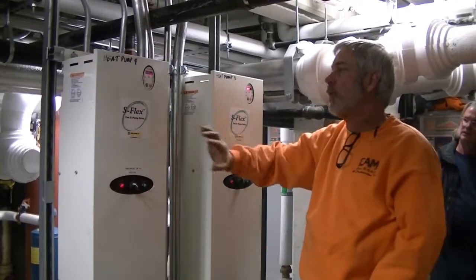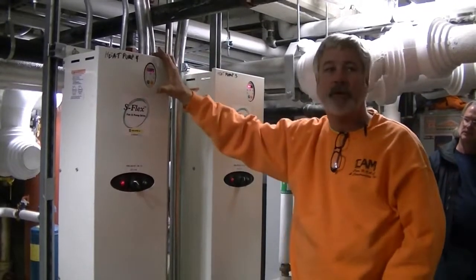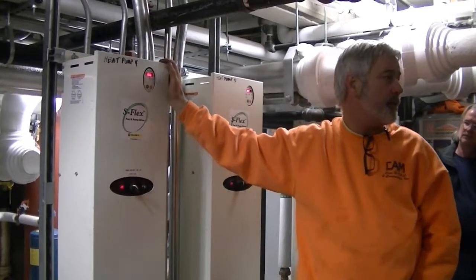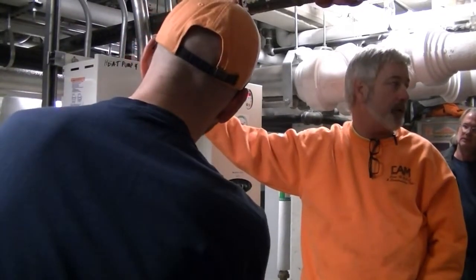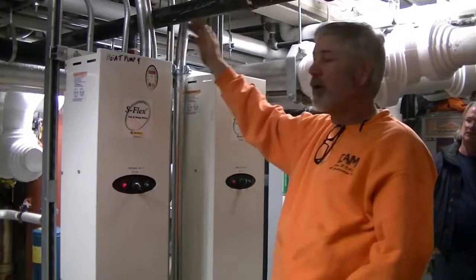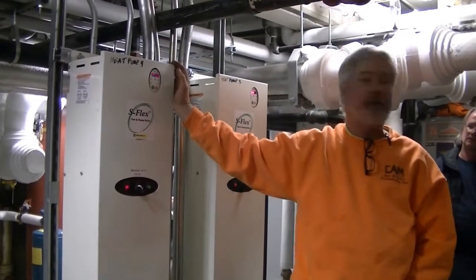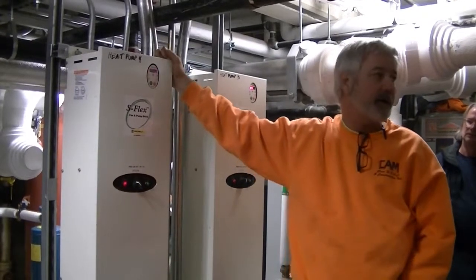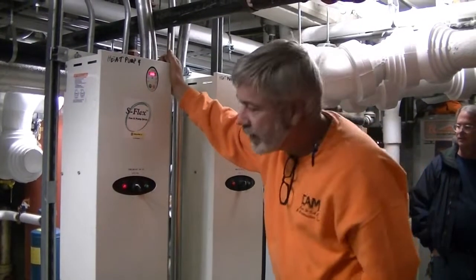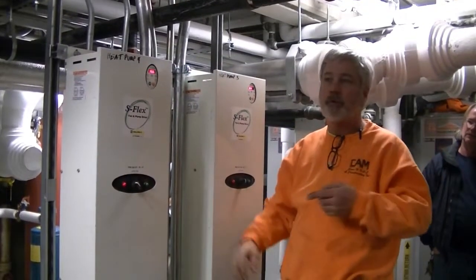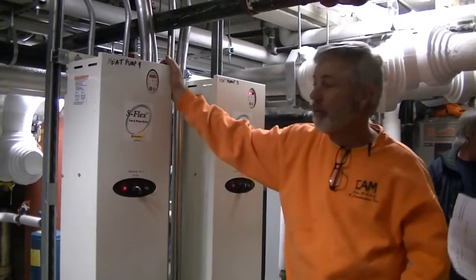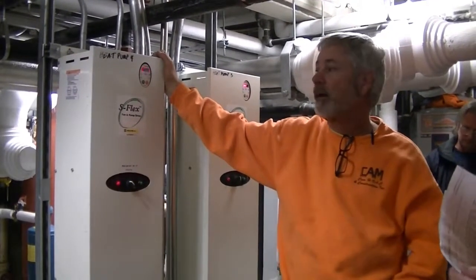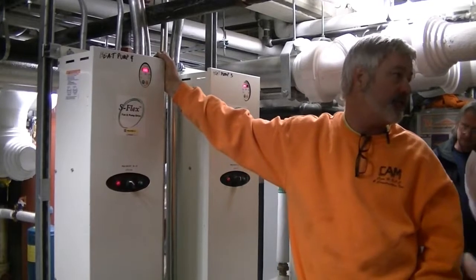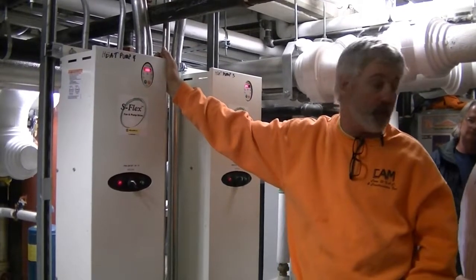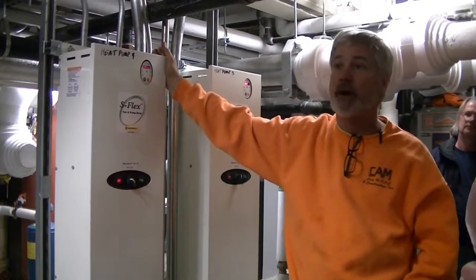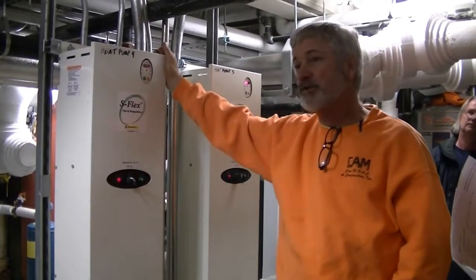If you ever have to put this drive in the local control mode, it needs to be monitored. You can blow the pump. If you put this in local, you turn it up to 40 or 50 hertz, you walk away thinking, that's all we need to do, we'll call the vendor. That's not the case, because if the zone valves start closing down, if the differential gets too high, you can do damage to the internal parts inside the pump. You could blow the seal, you could take out a bearing, you could create excessive noise in the system. You could have zone valves that will refuse to open because the pressure is too great on the high pressure side of the valve.